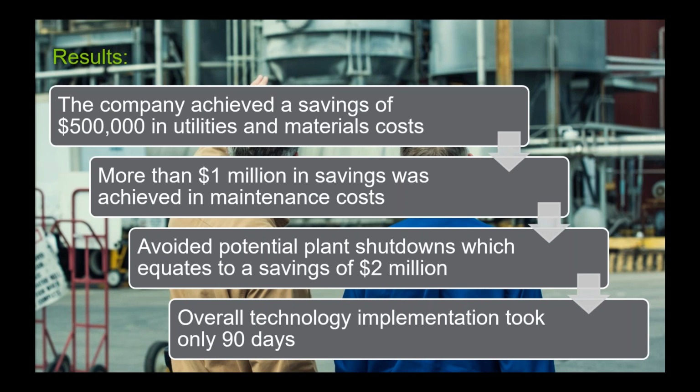That would go into the intelligence, and we'd have a nice report saying, okay, here's the steam traps that have failed. Here's the mean time between failures. Here's the dollars it's costing us. So we could easily prioritize, well, here's the traps we need to work on because it's costing us $30,000 a year or $40,000 for these traps. The other traps may be $1,000 or $2,000. So we could prioritize using all the software together what to work on.